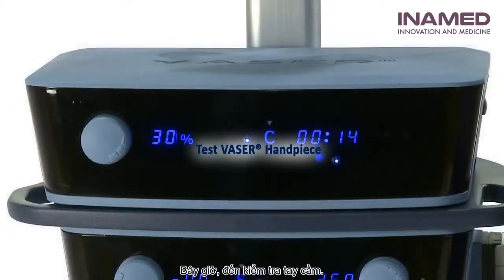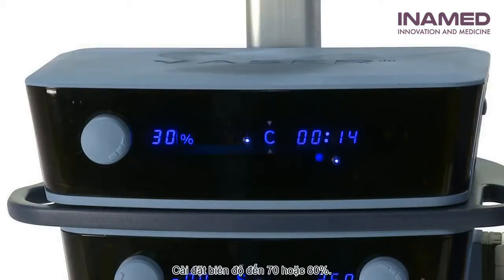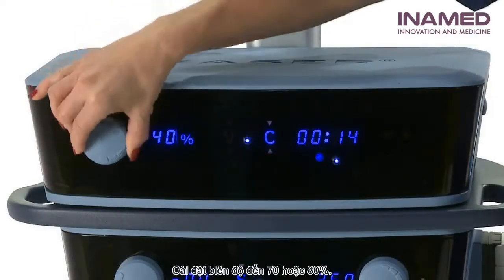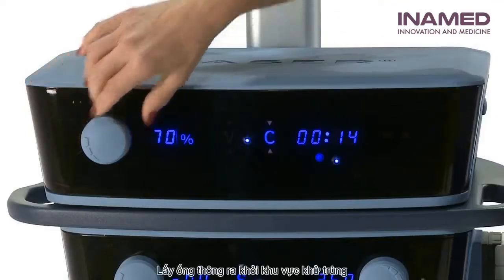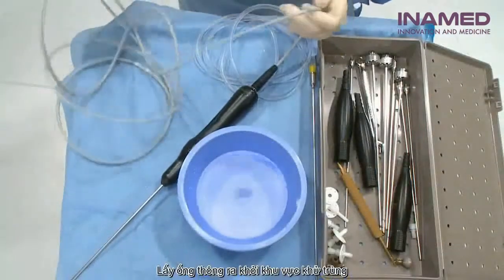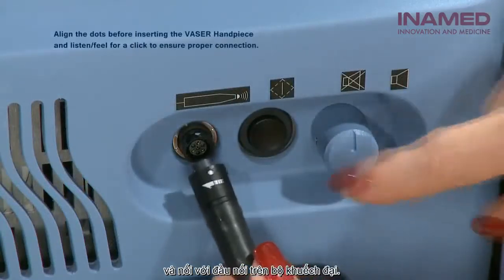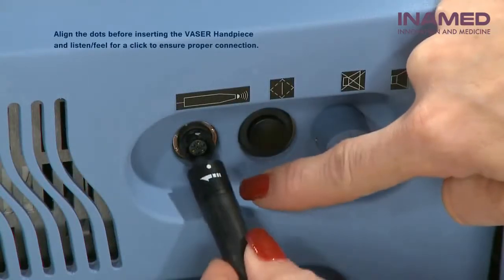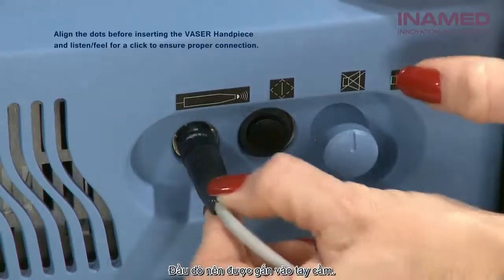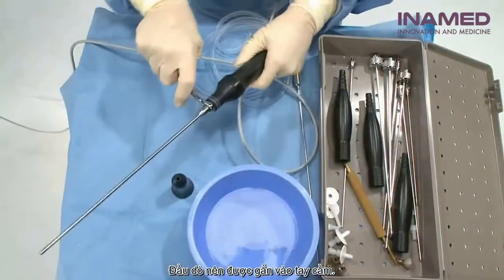Now, test the Vaser handpiece. Set the amplitude control to 70 to 80%. Pass the Vaser handpiece connector out of the sterile field. Connect it to the receptacle on the Vaser amplifier. The Vaser probe should already be attached to the Vaser handpiece.